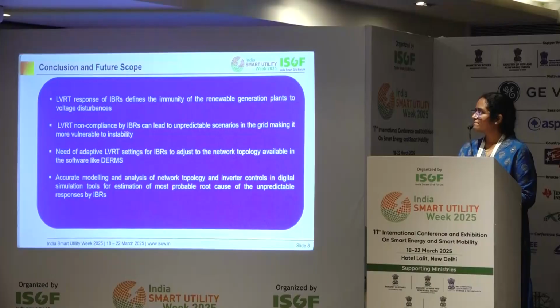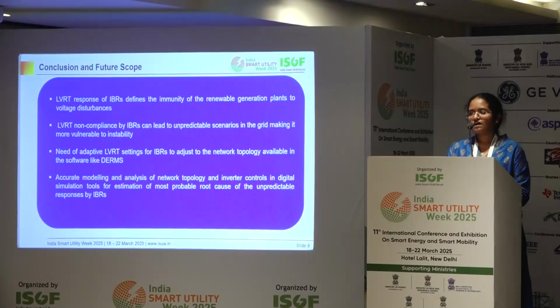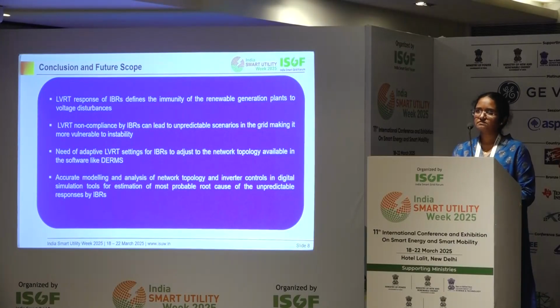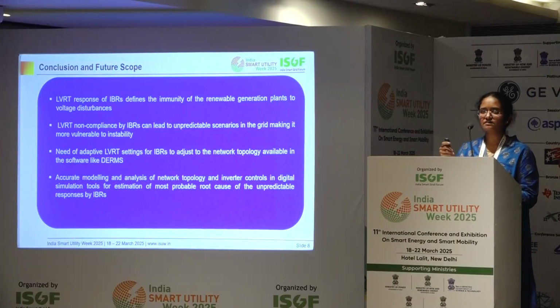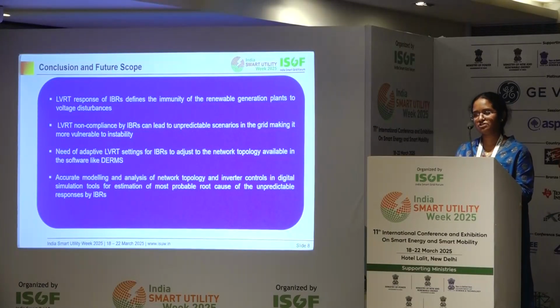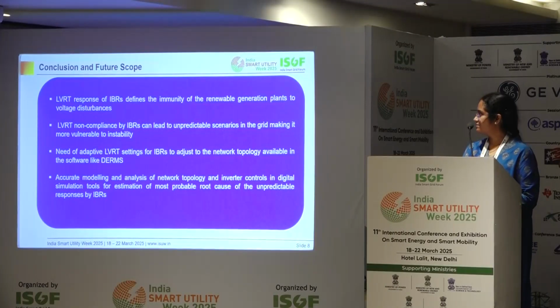So what we are proposing is, in most LVRT settings, it will just take the reactive power requirement or the K factor, which gives a linear increase in the restoration of the voltage dip from the actual level, as shown in the LVRT curve. So it just takes those settings for voltage restoration and reactive power, but it also has to consider the topology of the grid to which it is being connected.